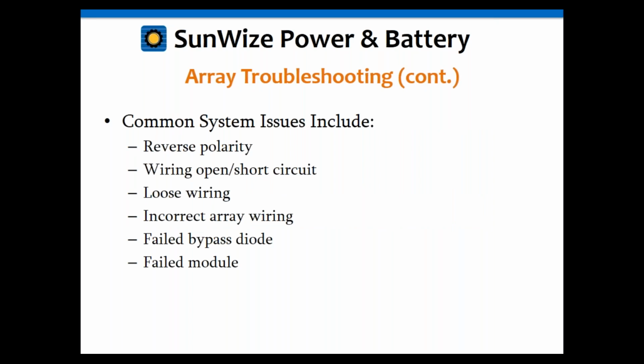With the open circuit voltage test, you can find several things. These are the common things you can look for. You can look for reverse polarity. You can find open wiring or short circuit wiring. A good example of open wiring was what I showed you earlier, that photo of the wire, literally the array output wire right by the MC connector that had failed. Somehow the insulation got damaged and it corroded and it broke apart. Loose wiring, that's another common one, as I mentioned earlier, especially with the thermocycling and the junction boxes.